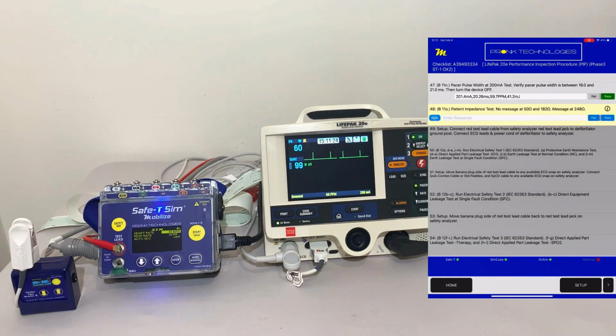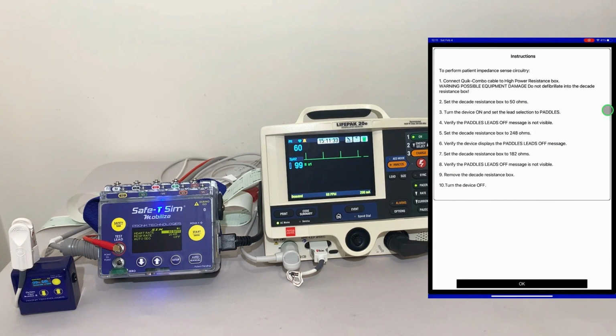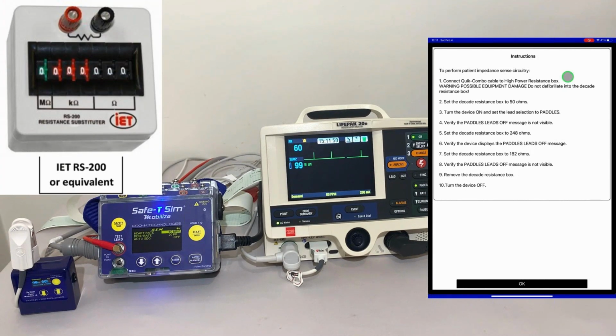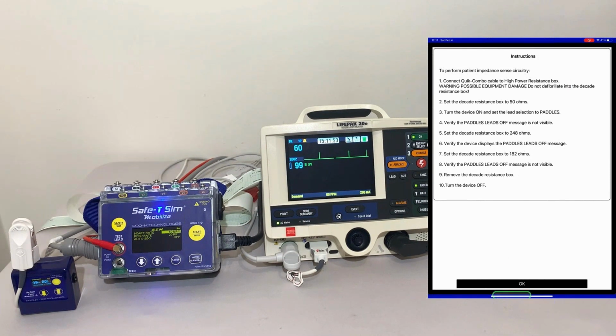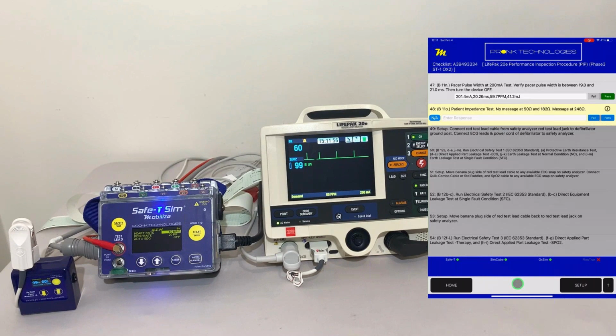The next thing we want to do is a patient impedance test. For this test, it's really taking a decade box, a resistance box. You connect it up to the ECG leads to confirm at what resistance the medical device detects a leads off condition. In this particular case, they want you to use a high power resistance box, which is specified in the service manual. We'll show you the model number here in a moment. You can purchase that and use that to do this leads off test, to do that basic resistance test to confirm at what impedance it detects the leads off and a no leads off message. We've done this prior, so we're going to go ahead and save time, go on to the next test.